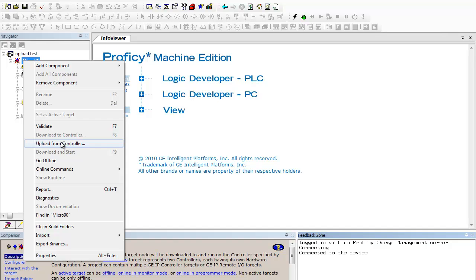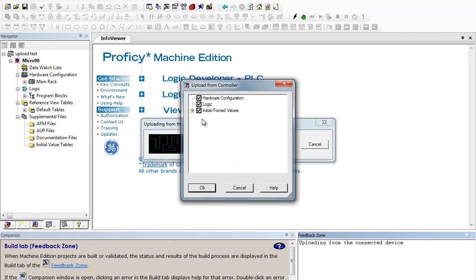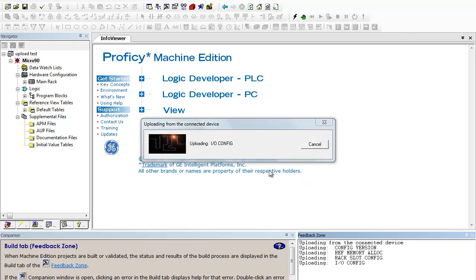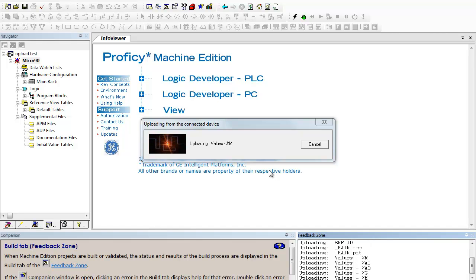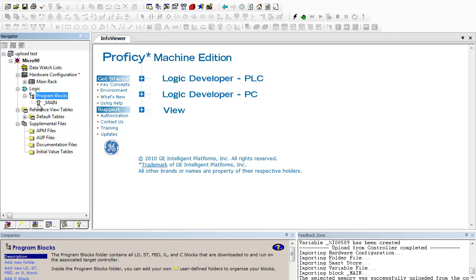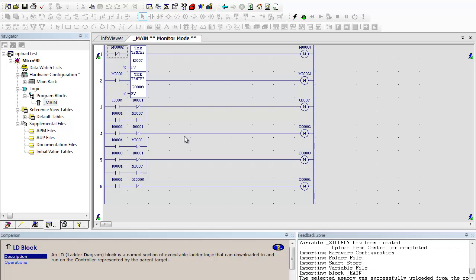Let's upload the program that is in it. I want to go ahead and upload everything so it is all up to date. When prompted 'Do you wish to overwrite the current?' — yes. This is useful if you are walking up to a machine to troubleshoot it and you did not have anything you wanted to do to it other than troubleshoot it, and you wanted to get the logic out of it. Main is where the logic is going to be stored, so we can double-click that. This is the actual logic that is inside of it and running. It is not a big program — this is just a test we put in our trainers so we can test the lights and everything before we send them out.